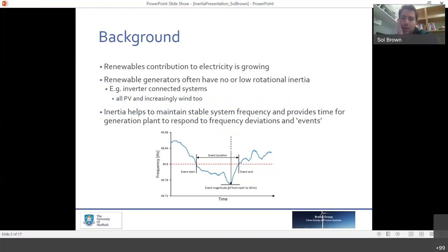So let's move on. I guess the background to all of this conversation is really that with the deployment of more renewables, the total amount of inertia on the system is going to reduce. Often renewable generators don't have any inertia or have low rotational inertia, for example some types of wind turbines. Because largely they're inverter connected, you lack the inertia which helps with the frequency events that you really want to manage. So inertia is an inherent property, given from the conservation of momentum of rotating masses, that helps provide some immediate response to power imbalances on the system.